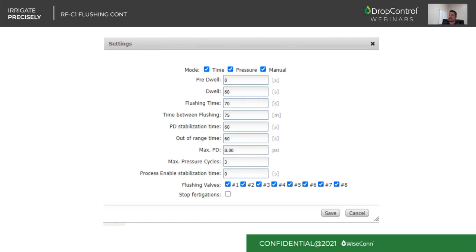Any time that a parameter is changed, it is going to be applied on the next cycle. So if the system is actually flushing and you change multiple parameters and you click on the save button, the actual flushing cycle won't be modified. So once the cycle ends, all these new parameters will take place for the next cycle.